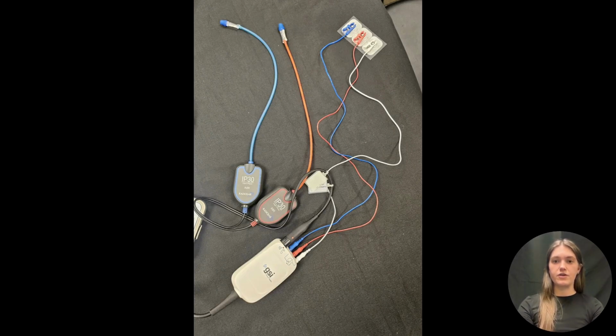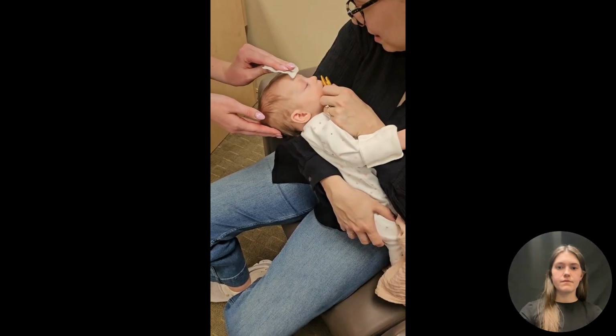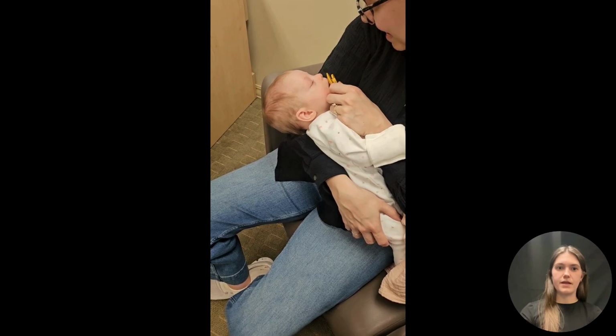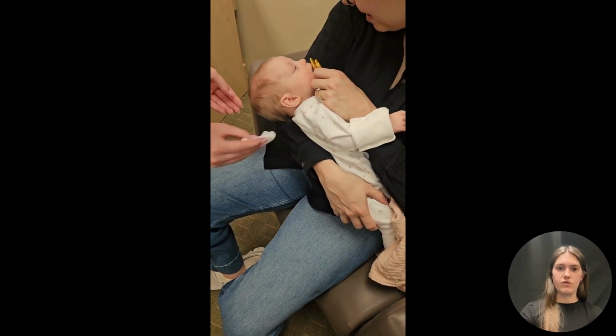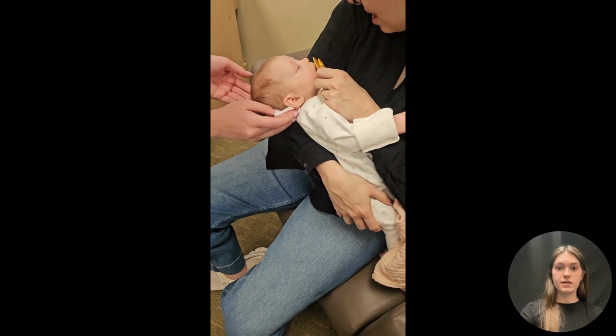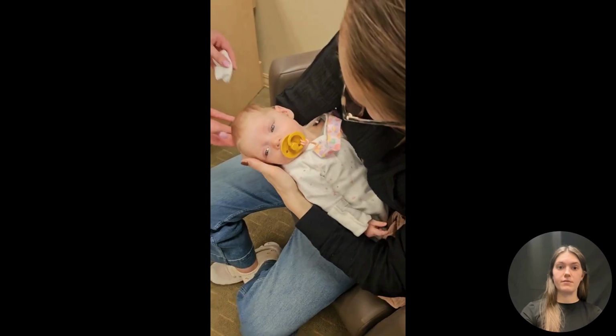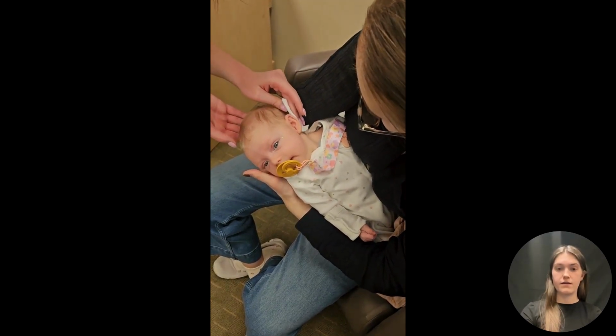The ABR screener you are using has two parts, the transducers and the electrodes. The transducers are what you put in or on the baby's ears to present a soft sound. The electrodes are what you stick to the baby's skin to measure the brainstem's response. The screening equipment is measuring how the auditory system responds to sounds that are played through the transducer. Correct setup for ABR screenings depends on the equipment, so review the user manual for the recommended setup. You should always clean the baby's skin, then place the electrodes in the recommended places, often on the head and neck.